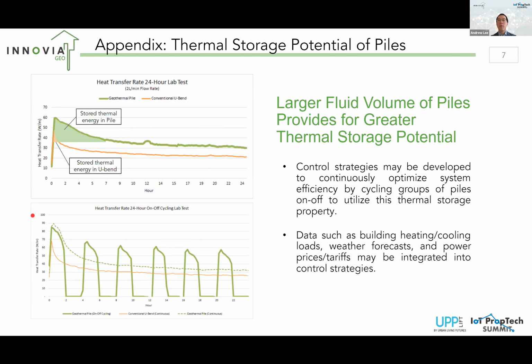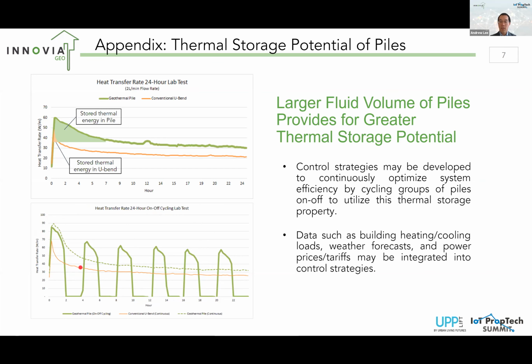And so with this property, we can start looking at using the piles almost like a natural rechargeable thermal battery, by actively letting it rest and naturally exchange heat with the ground. And that's this test here, which is another 24-hour test, which turned on a pile for 2 hours, let it rest, and then turned it on again. So what we see in the shaded area here is that higher heat transfer rate during that period.